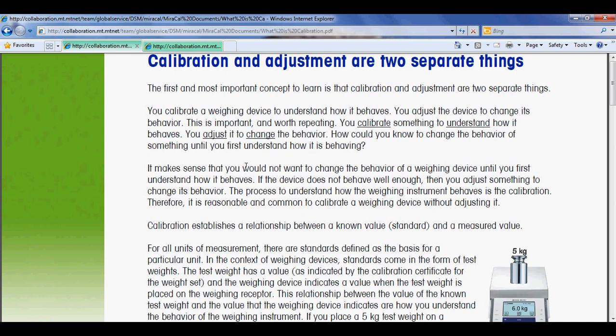So it makes sense that you would not want to change the behavior of a weighing device until you first understand how it behaves. If the device does not behave well enough, then you adjust something about it to change its behavior. So the process to understand how the device or the weighing instrument behaves is the calibration. Therefore, it is reasonable and common to calibrate a weighing device without adjusting it.